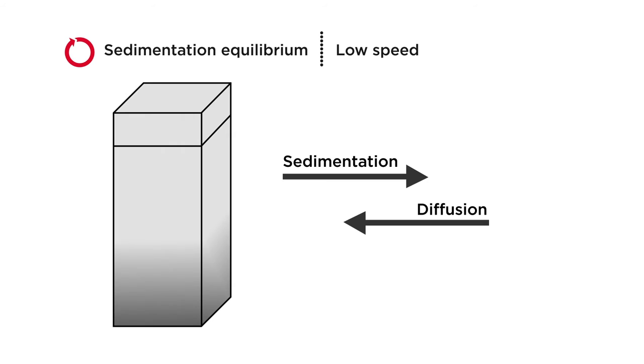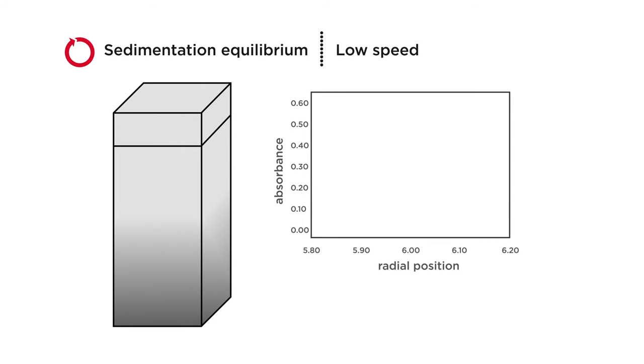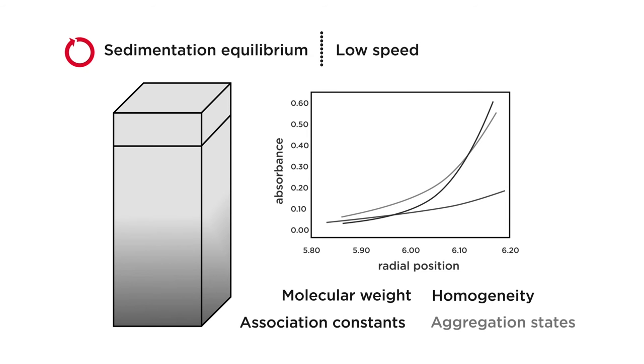The data is plotted as sample absorbance versus radial distance from the center of the rotor where the slope of the curve provides information on complex molecular weight. The distribution movement over time is used to calculate the molecular weight and homogeneity of the solution under study, as well as association constants and aggregation states.